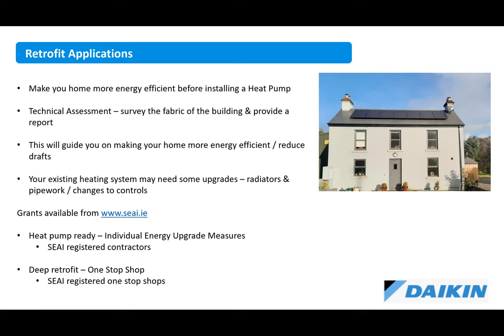So for retrofit, it's a little bit more complex because you're dealing with an existing building that has been built prior to the current building regulations. And in that regard, it's definitely recommended that you consider making your home more energy efficient before you install a heat pump. And this is very much the guidelines coming from SEAI, Sustainable Energy Authority of Ireland. So their recommendation is, if you want to put a heat pump into your existing home, that you should firstly carry out a technical assessment. And this is a survey on the fabric of the building. So it's going to look at the insulation, the quality of the windows, the amount of leakage of heat out of the building or air changes within the building.